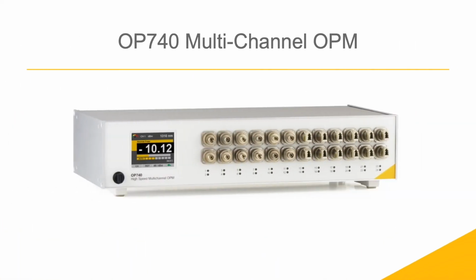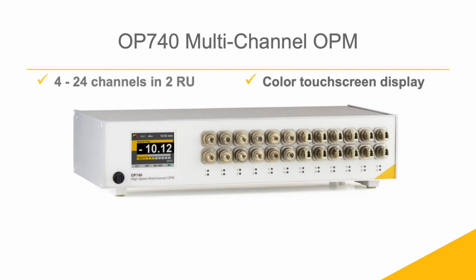The OP740 is significantly different than the OP710. The most obvious difference is the color touchscreen display. While it uses the same detectors as the other models, it can take up to 125,000 readings per second. This makes it an ideal solution for stability measurements, environmental testing, and production testing of certain optical components.